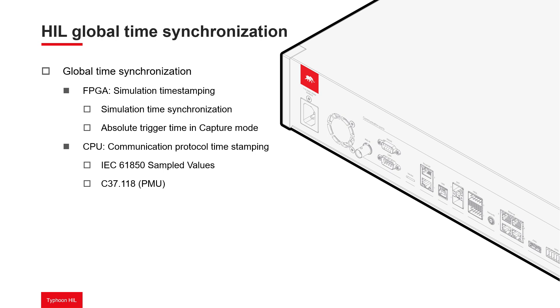On the CPU side, communication protocols like IEC 61850 sampled values and C37.118 provide timestamps within the data packets they transmit. The HIL device CPUs can leverage this information to include accurate timestamps within any outgoing Ethernet packets. This ensures both the data and timing within the HIL system are synchronized, regardless of the original time synchronization source.